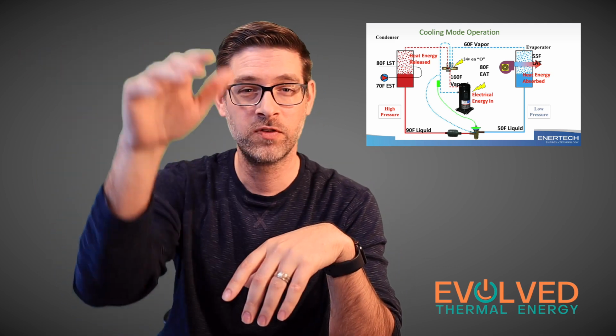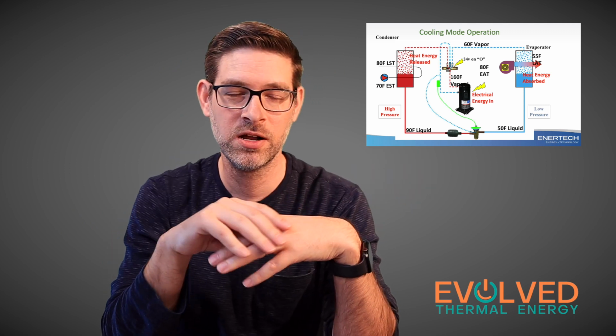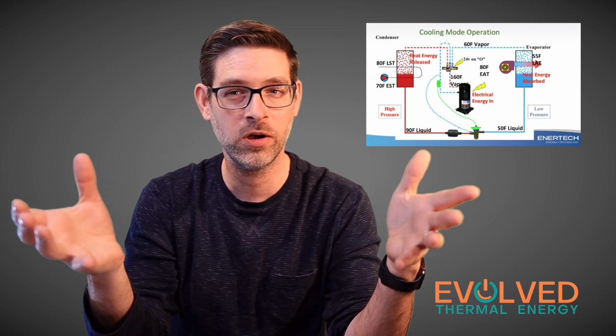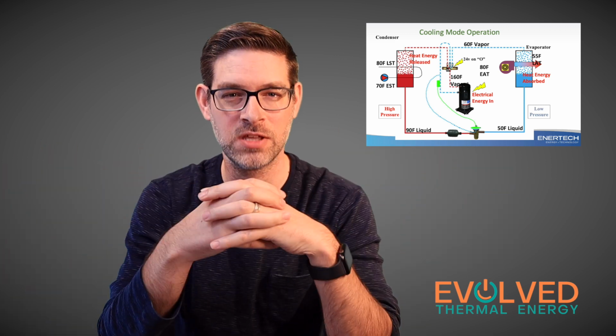So that's what it does. When you put your hand over top of the condenser, you've got much warmer air than the ambient air outside. The condenser is a fan over a coil, and that's just moving air over that coil, releasing that heat into the outdoor air. And so when you think about heat pump, an air conditioner is a heat pump. The difference between an air conditioner and the heat pump that we're talking about today is that a heat pump's reversible. So it can choose where the condenser and where the evaporator are.